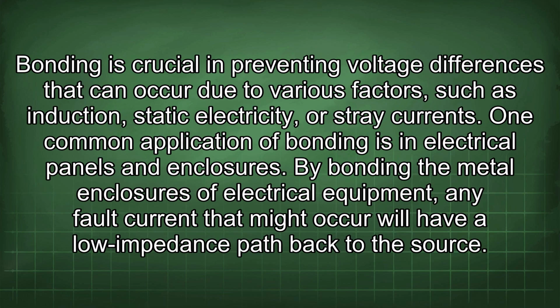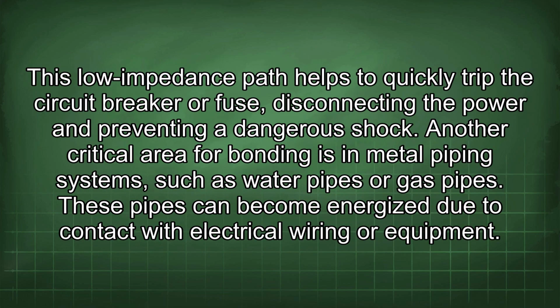Bonding is crucial in preventing voltage differences that can occur due to various factors such as induction, static electricity, or stray currents. One common application of bonding is in electrical panels and enclosures. By bonding the metal enclosures of electrical equipment, any fault current that might occur will have a low impedance path back to the source. This low impedance path helps to quickly trip the circuit breaker or fuse, disconnecting the power and preventing a dangerous shock.